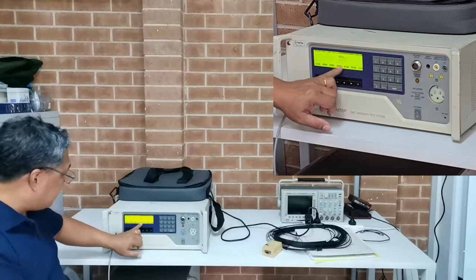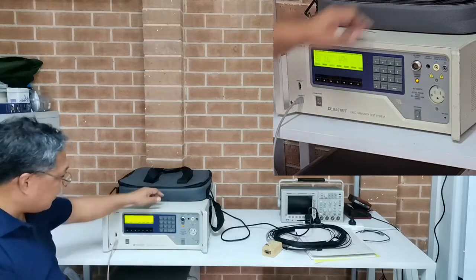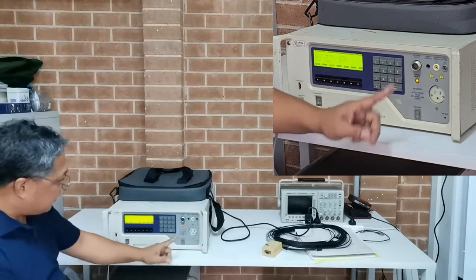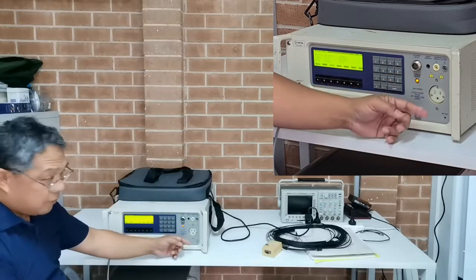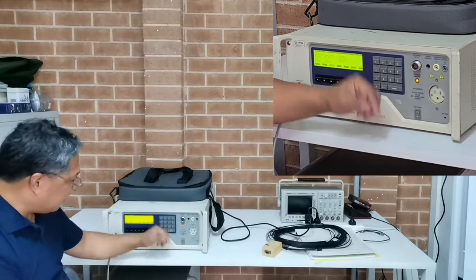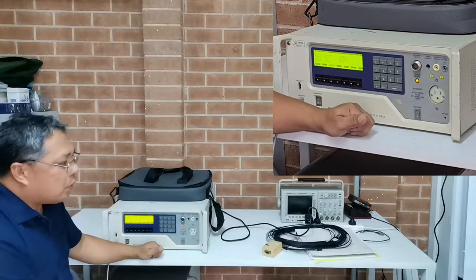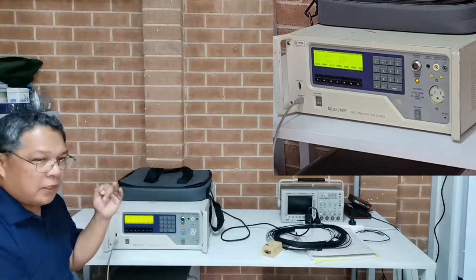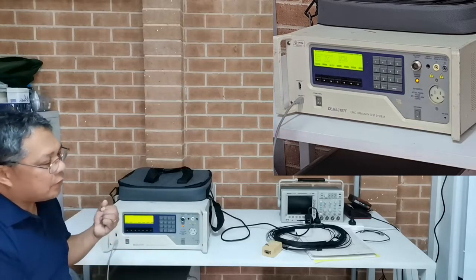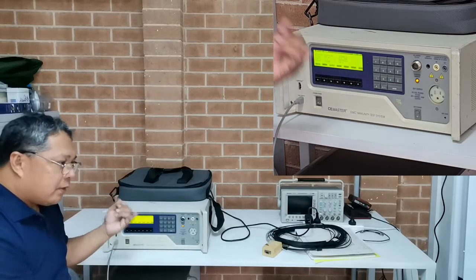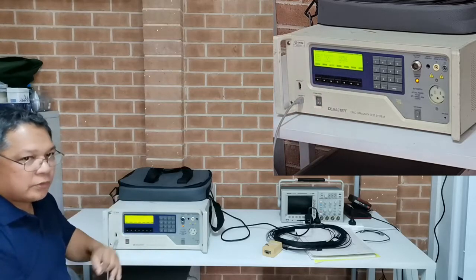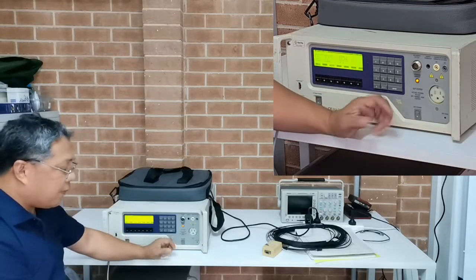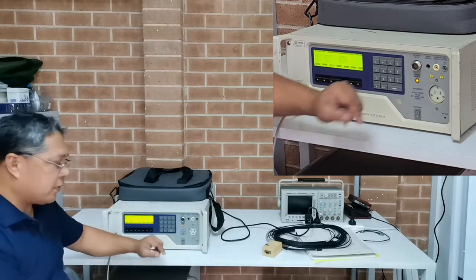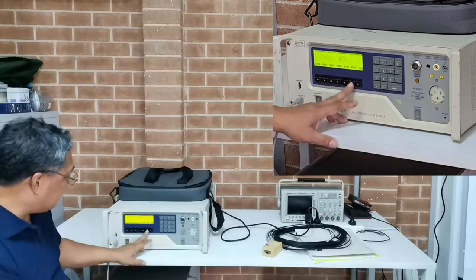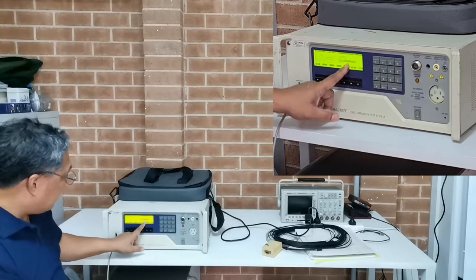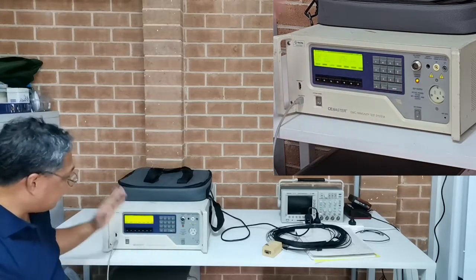We can try this one in 60 seconds. First run, and you have this voltage present, and what happens is you have the high voltage burst into one of the lines, which is line 1. For the new standard, you apply the burst on all lines: L1, L2, and PE. The old standard only required you to apply between line 1 to earth, line 1 to line 2, and line 2 to earth. But in the new standard, you must apply on all the lines simultaneously. So for this one you select L1, L2, and PE, and that applies to all lines together.